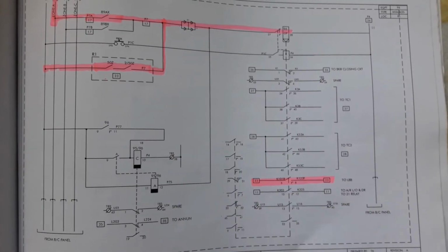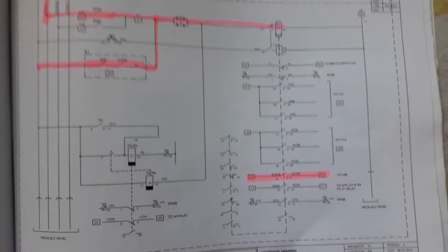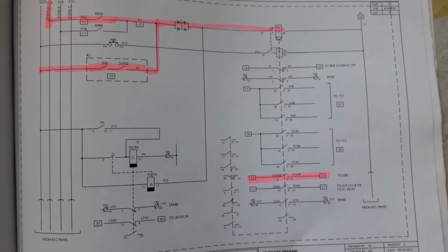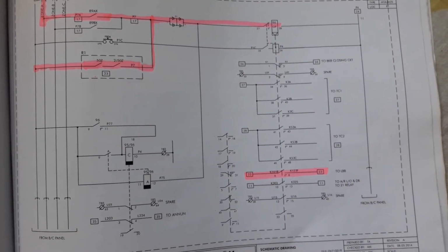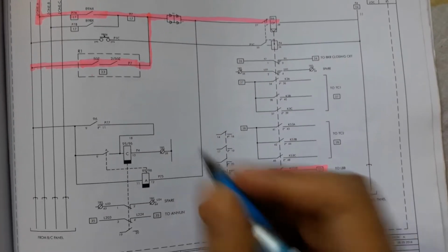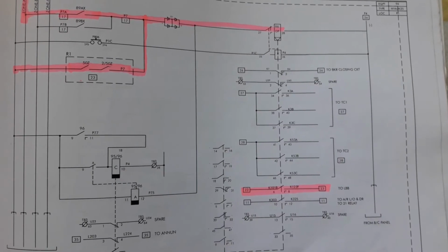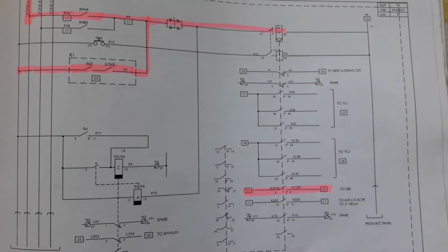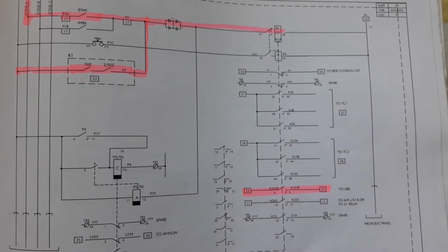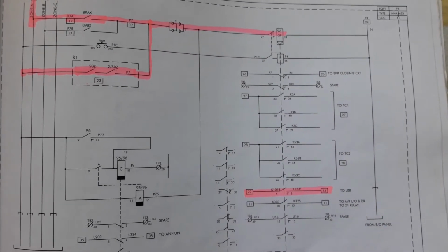We already discussed that if the circuit breaker fails to clear a fault, then LBB protection will operate, or 50Z and 50Z timer, that is 2 by 50Z, will also operate. On operation of LBB protection relay, the bus with which the failed circuit breaker is connected will become dead or de-energized.